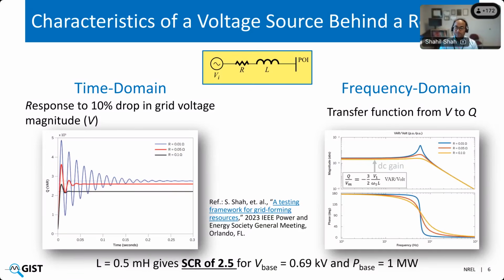One is that most synchronous machines, or I should say all synchronous machines within a particular frequency range, behave like a voltage source behind reactor. As power system engineers, we routinely represent synchronous machines by this behavior. The second reason is that when we test inverter-based resources and now large electronic loads for performance, we usually test them in a single machine infinite bus setup, where we represent the grid by this very simple topology, which is voltage source behind reactor, and we see under what grid strength conditions that device remains stable. So that is the second reason why we want to use this as a framework for quantifying the voltage source behavior. Now, there are two ways to do that. One is the time domain approach, where we can quantify the behavior of a resource to act as a voltage source behind reactor. And the second approach is in the frequency domain.